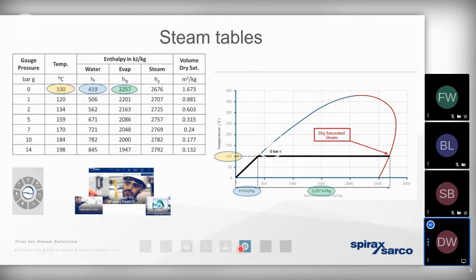And we've mentioned in previous presentations that water, the raw ingredient of steam, has got a specific heat capacity of 4.19. In other words, if we want to heat 1 kilogram of water at the process, then we need to ensure that we add 4.19 kilojoules of energy to it just to raise the temperature by 1 degree. So if we want to raise water from 0 degrees to boiling point, which at atmospheric conditions or 0 bar gauge we know is 100 degrees, you can see we need to add 419 kilojoules of energy into it.